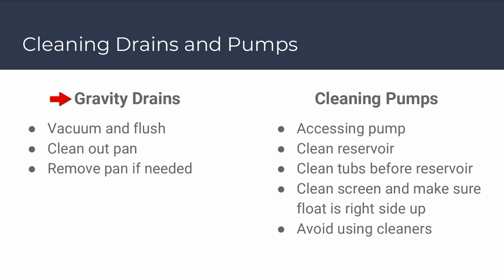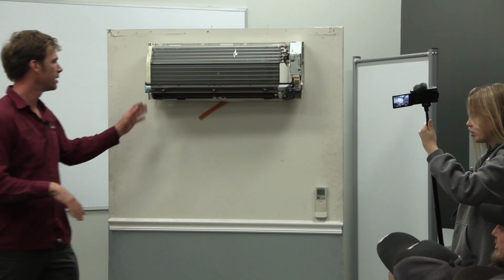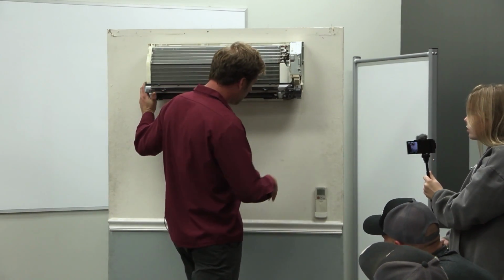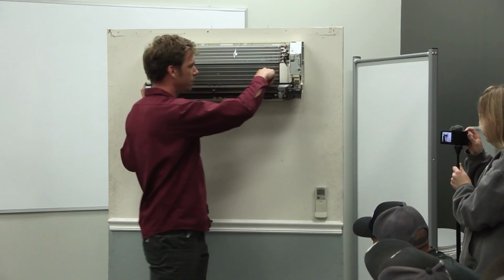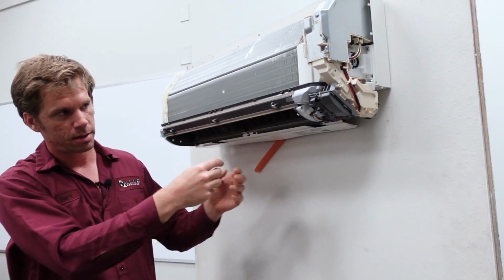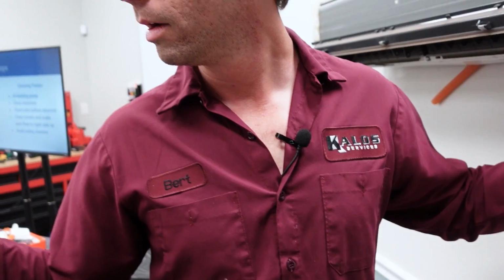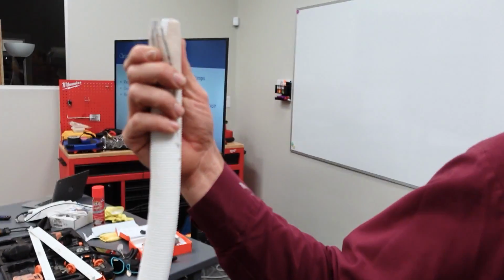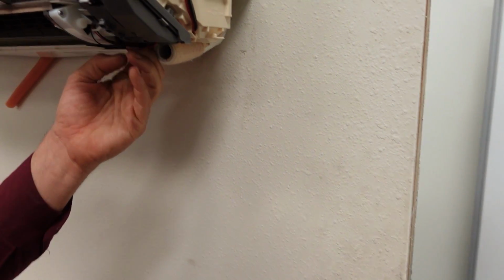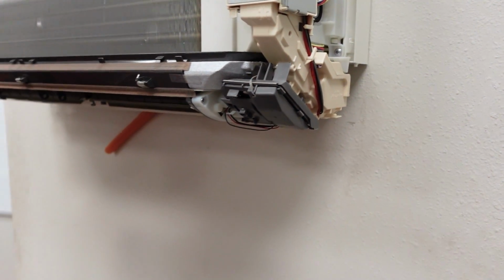Gravity drains, simple. You guys know what to do there, right? Hook up a vacuum, dump water through. The only other thing I was going to point out is that your pans, you can actually remove to clean them. If there's a lot of junk built up, there's a clip on the back where your drain is, right there. You pull that down and it slides out of the pan, and then you can take the whole pan off of the system.